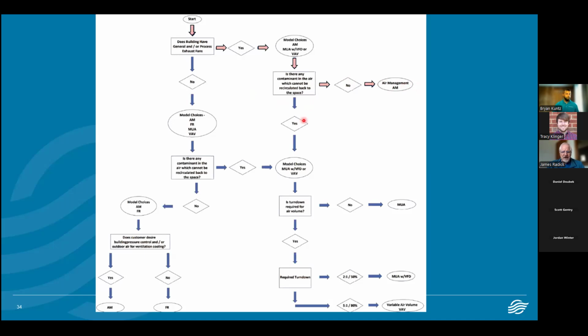And if you go down that left-hand column, let's say that first decision tree asks, does it have general and/or process exhaust? No. Okay, let's go down. We're still looking at all the options here. And is there any contaminant in the air which cannot be recirculated back to the space? No. Then you just follow on. 90% of the time, you're going to find that a variable volume recirculation mixed air unit is going to be the choice for the buildings, whether it's warehouses, because of the dock doors opening and closing.